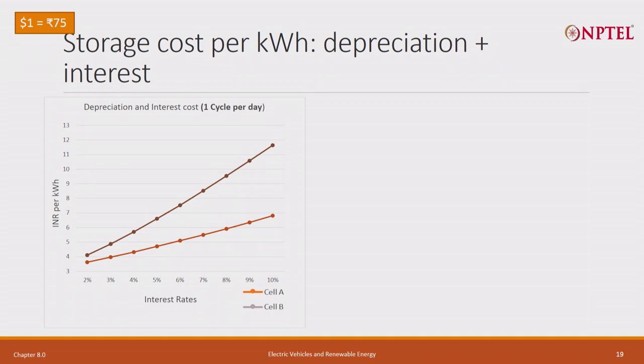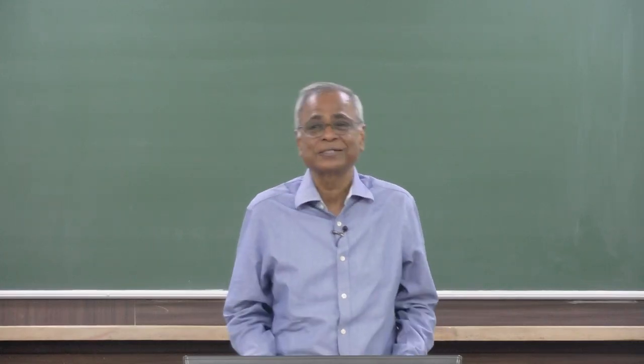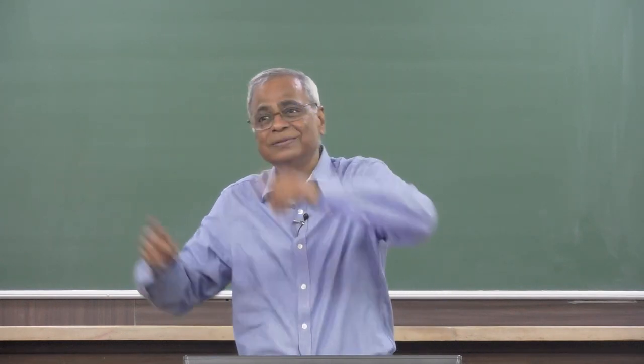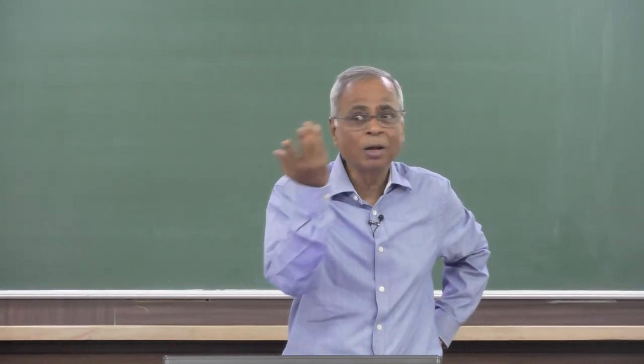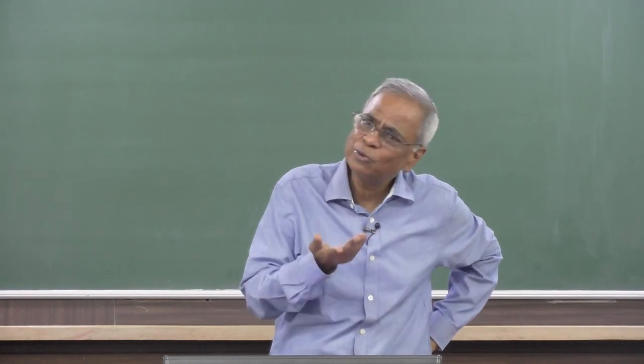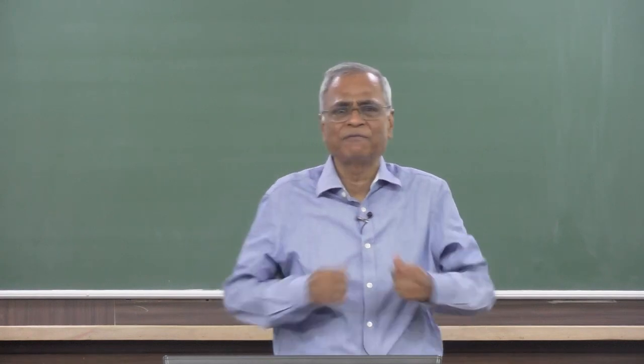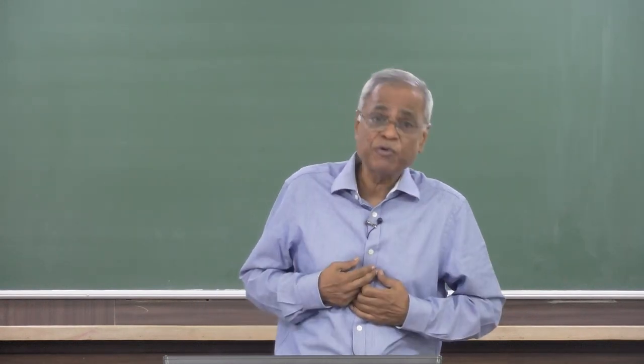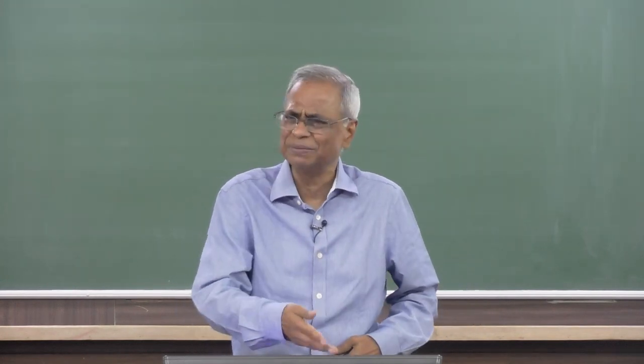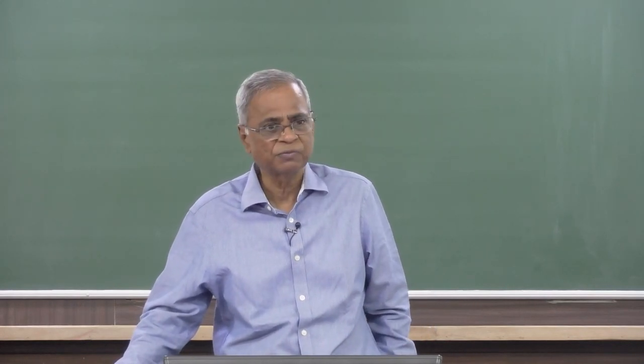This is a very simple exercise and I want to warn — there are plants being set up by government and private sector, advised by Europe and United States. They come and say put LTO battery; in their country it is probably equal or better. They have not even understood that Indian interest rate is 10 percent or higher. Government of India sanctions the money without doing simple calculations — their advisors come and give them guidance and that is it. Advanced NMC will become the better choice for now, though that may change tomorrow.